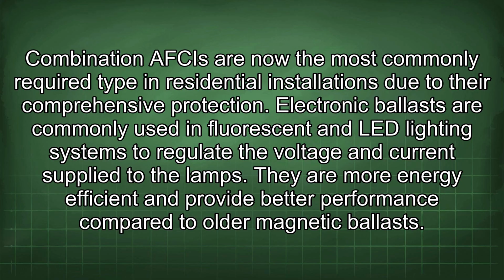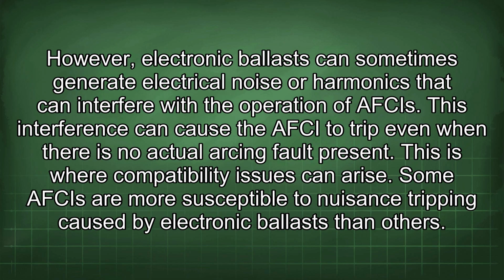Electronic ballasts are commonly used in fluorescent and LED lighting systems to regulate the voltage and current supplied to the lamps. They are more energy efficient and provide better performance compared to older magnetic ballasts. However, electronic ballasts can sometimes generate electrical noise or harmonics that can interfere with the operation of AFCIs. This interference can cause the AFCI to trip even when there is no actual arcing fault present. This is where compatibility issues can arise.